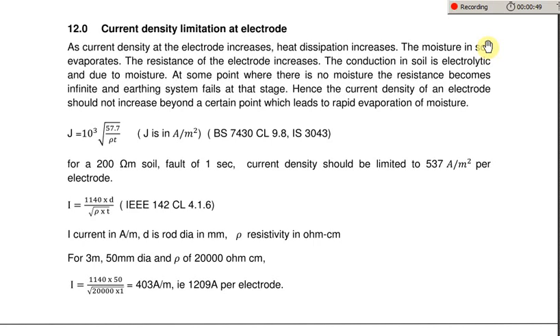And as the moisture content reduces, the resistance of the electrode increases. So at some point of time, when the moisture content is very very low or absent, the resistance of the electrode becomes infinite. This is as good as some conductor being cut.